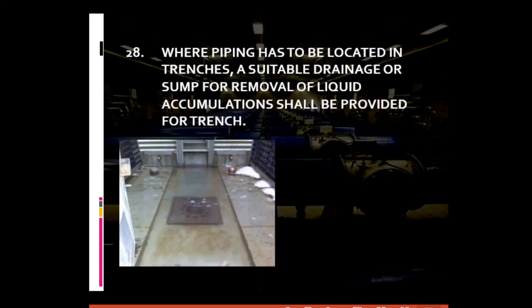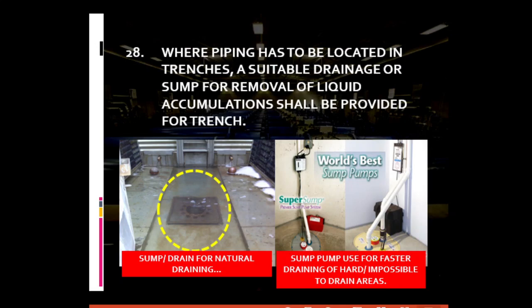For general piping requirement number twenty-eight: where piping has to be located in trenches, a suitable drainage or sump for the removal of liquid accumulation should be provided for the trench. Aside from steel branches, such trenches should also be provided with drains to prevent the piping line from being submerged, allowing easier monitoring and possible repairs. When natural drainage can no longer handle the accumulation of liquid, a sump pump is used.